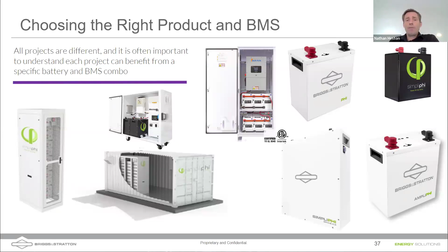When we get to very high power output and large systems, we go to high voltages because then we don't have to use massive 2-inch cables, like 350 kcmil and 500 kcmil. We can use smaller cabling if we go to high voltage, and that's a big reason we do that.